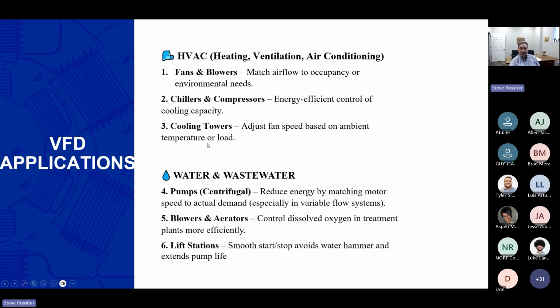Cooling towers is another interesting one. You know that that's probably, if you go and look at a manufacturer's catalog for two-speed motors, you see less and less of those now, because you can have 100% or 50%, perhaps with a variable torque two-speed motor, but with a variable frequency drive, if you need to operate at 70%, you can operate exactly at 70%. And you can adjust that based on the temperature of the water that that cooling tower is cooling. So we saw most cooling towers being replaced long ago with variable frequency drives.